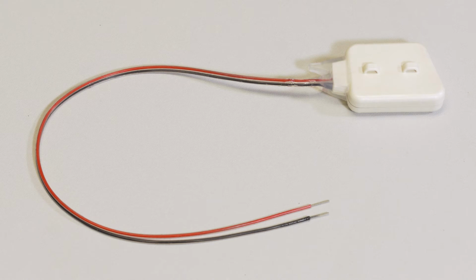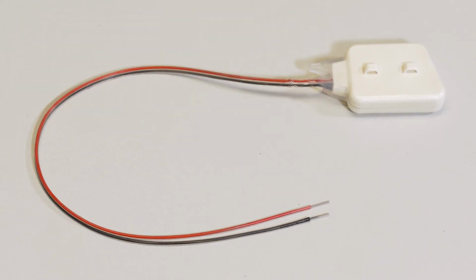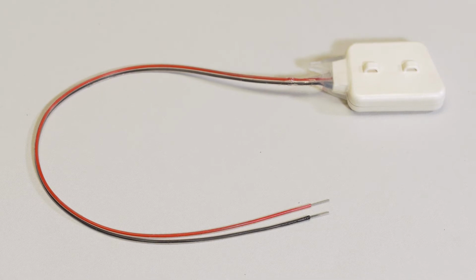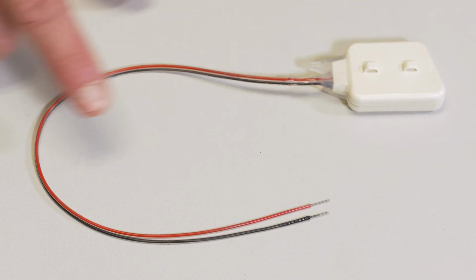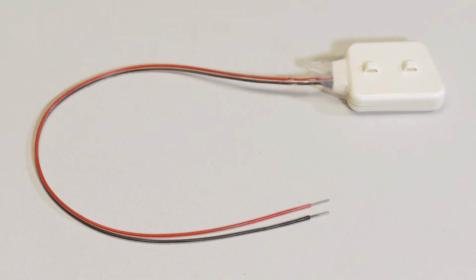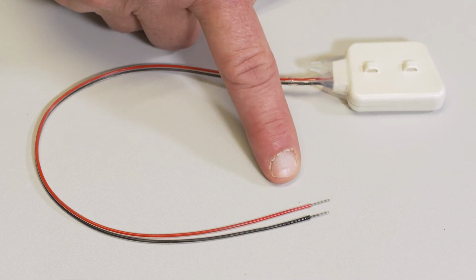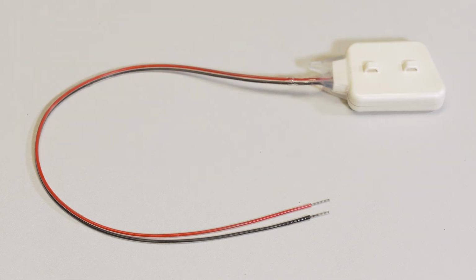This is the TR50B single biopotential RAT telemeter. This can be used to record a single biopotential signal. So it records the potential difference between the 2 electrode leads. If you were to record ECG, you could put them across the chest. EMG, you could choose a muscle to place the electrodes across, or EEG to record signals from the brain. The telemeter has suture tabs to hold it in place in the abdomen, and then the leads are tunneled to your recording site of interest. At the end of your experiment, you can explant the telemeter, trim the leads back slightly, re-sterilise your telemeter, and perform your next recording.